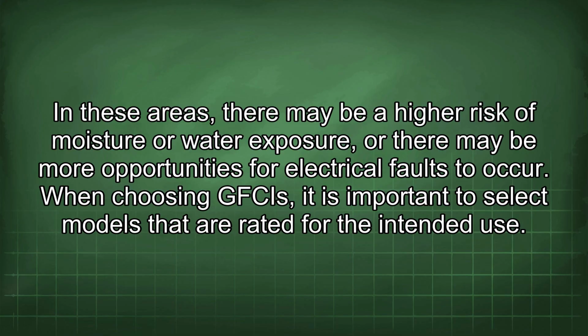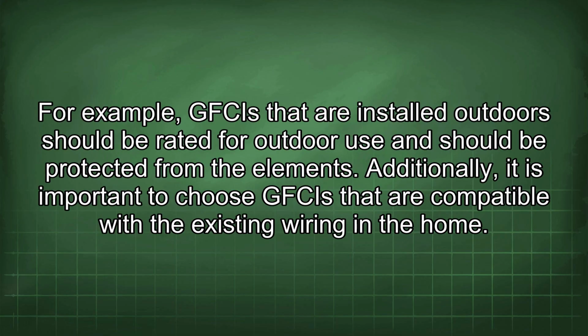When choosing GFCIs, it is important to select models that are rated for the intended use. For example, GFCIs that are installed outdoors should be rated for outdoor use and should be protected from the elements. Additionally, it is important to choose GFCIs that are compatible with the existing wiring in the home.